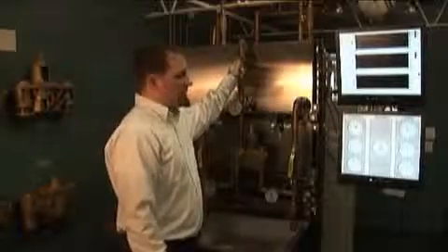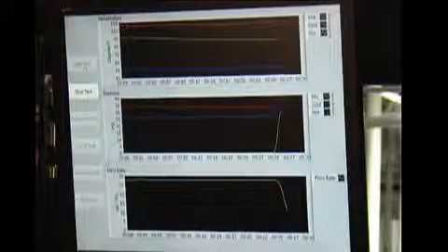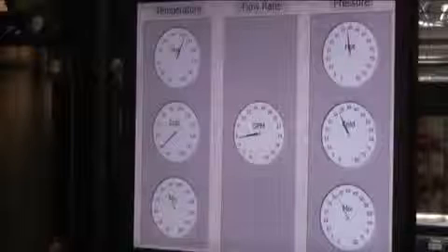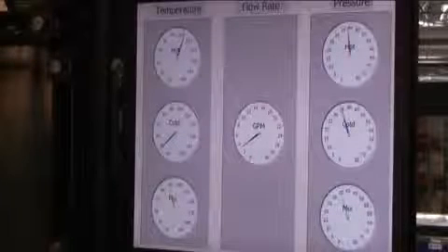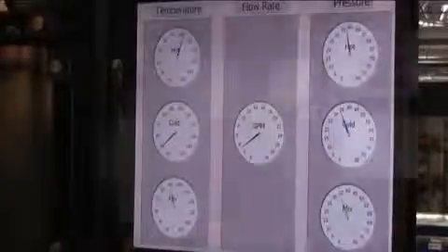This would be a typical flow rate if a drench shower or something like that was being used, but what if it were just an eye wash? And reduce it down to the flow about what an eye wash would do, and you can see we're still really holding temperature within a couple of degrees of that 85.